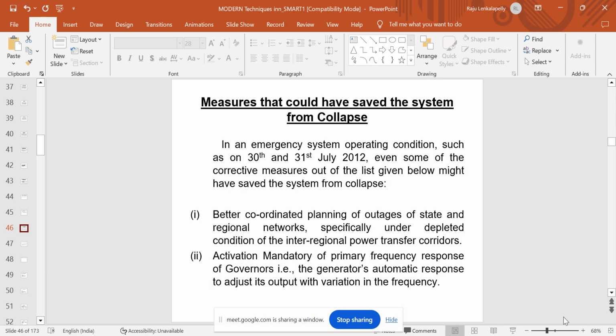The second point: when states overdraw power, they short circuit the governor, which is the heart of load frequency control. To keep frequency constant, the governor should come into the picture. But at the time, electricity board people in the respective states had disconnected the governor. So the committee now recommends mandatory activation of primary frequency response of governors, meaning the governor's automatic response to adjust output with variation in frequency.